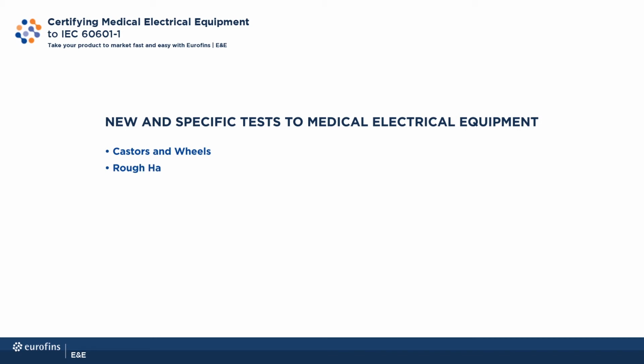Making sure that equipment can support 2 to 8 times its expected load, being able to read the label from a distance, making sure equipment is restored to safe state after a power outage, making sure equipment that is already connected to the body still works after a shock event, making sure equipment cannot be turned up beyond safe limits, making sure that equipment won't spark in an oxygen-rich environment, and making sure that the material of the applied part does not cause toxic reactions or immunological rejection.